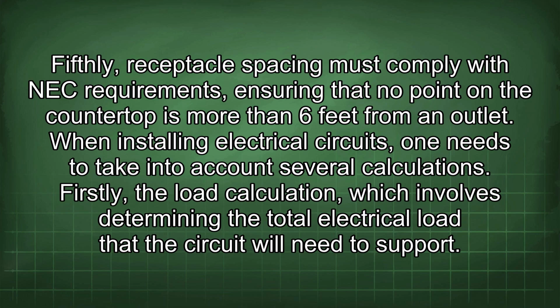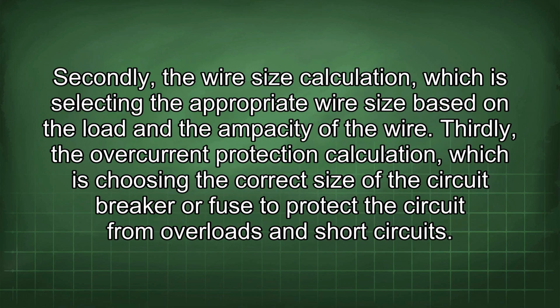When installing electrical circuits, one needs to take into account several calculations. Firstly, the load calculation, which involves determining the total electrical load that the circuit will need to support. Secondly, the wire size calculation, which is selecting the appropriate wire size based on the load and the ampacity of the wire. Thirdly, the overcurrent protection calculation, which is choosing the correct size of the circuit breaker or fuse to protect the circuit from overloads and short circuits.